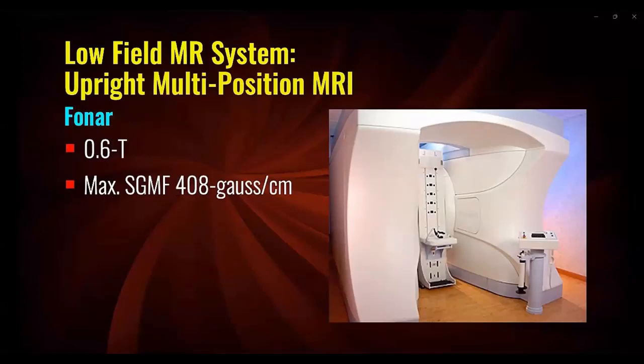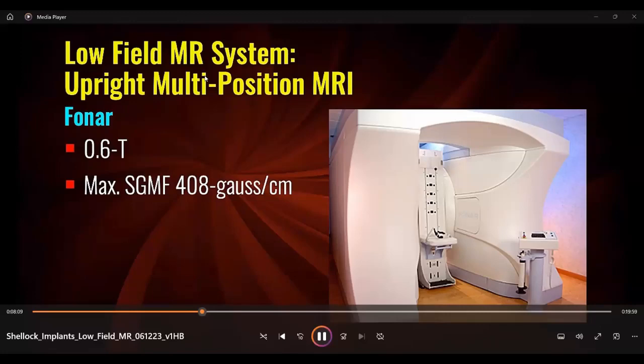FONAR's 0.6 Tesla upright multi-position MRI is an MR system that can scan patients in any position, including sitting, standing, during flexion and extension, or lying down. This scanner has a horizontal field that is transverse to the patient and has a maximum spatial gradient magnetic field value of 408 Gauss per centimeter.